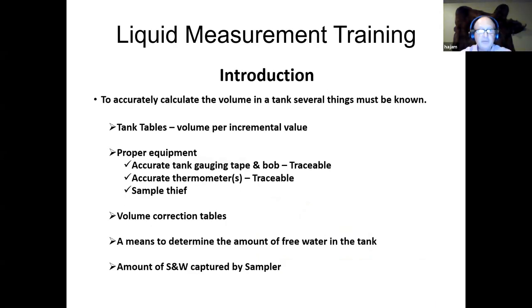To accurately calculate the volumes in a tank, several things must be known. We have to have the tank tables. We have to have them to understand what volume per incremental value there is in every foot, inch, tenth of an inch. We have to know those volumes, and that's determined by tank calibration. And like I said earlier, that is typically done by a third party because it's a very strenuous process, especially for tanks that are being used for custody transfer.